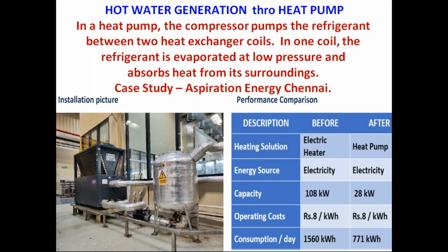Heat pump is an innovation especially happening in the hospitality segment. I am just touching on where all energy conservation is possible in different types of industries and processes. You can see the consumption of the existing heater is almost 108 kilowatts. This consumes only 28 kilowatts. You can see the difference in consumption: instead of 1560 units per day, it has come down to 770. Almost 50% energy savings is possible by using a heat pump, especially in hot water applications.